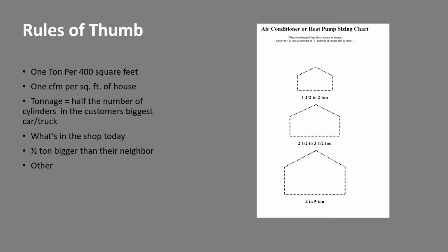1 ton per 400 square feet has been around for a long time. If that was ever correct, it was probably for a largely uninsulated house with single pane windows. So if it was ever correct, it's probably not correct today in modern homes with insulation and a higher degree of air tightness. The 1 CFM per square foot of house, I know that's out there.